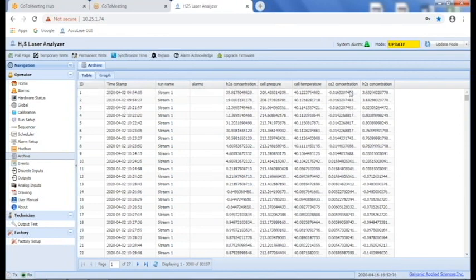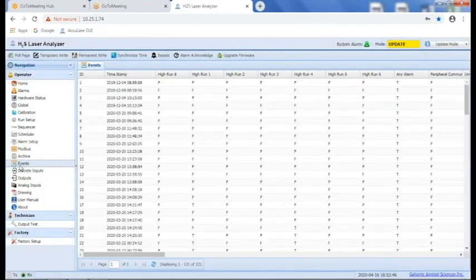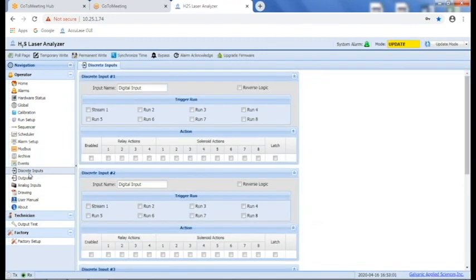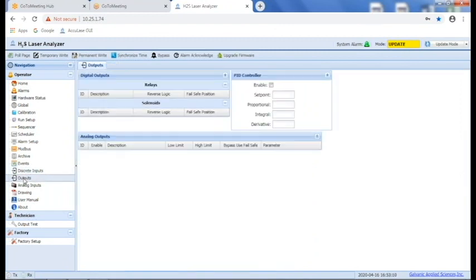A similar thing is the event logger, which shows you different statuses of the analyzer itself on a per run basis. So if there were any alarms active, you'd be able to suss them out here. We have discrete inputs that are available for either discrete alarms like pressure switches and that sort of thing, or they can also be used to initiate runs.